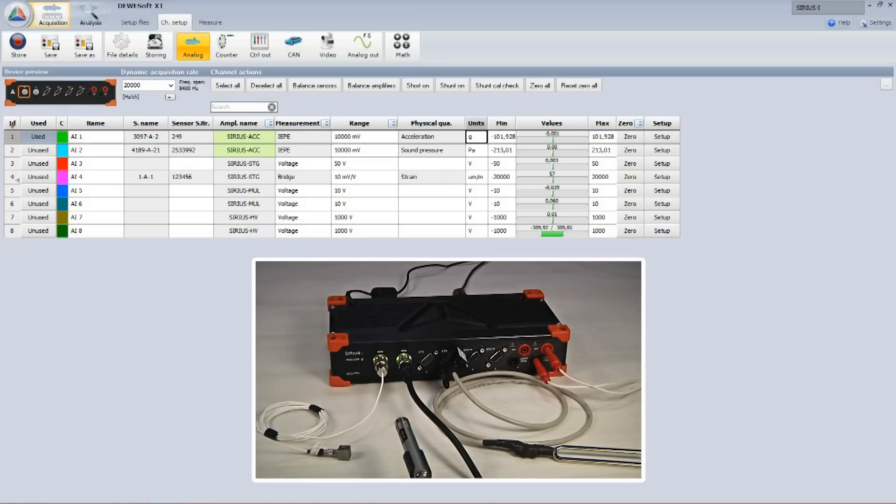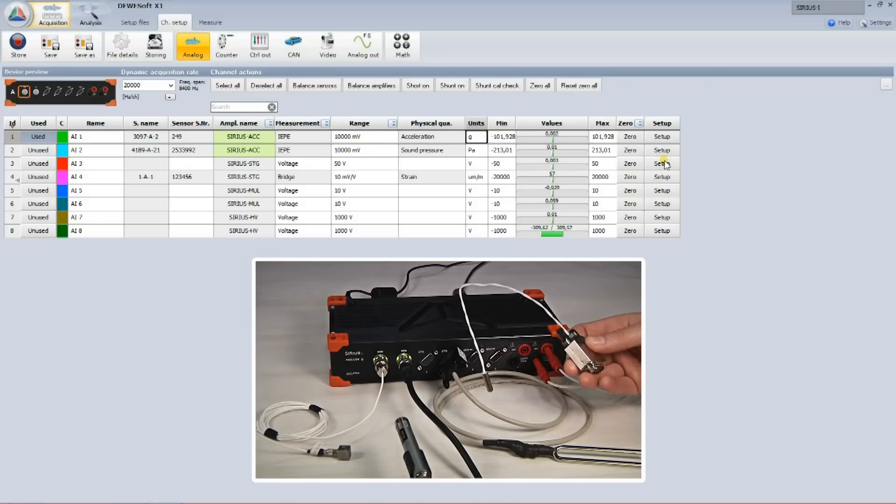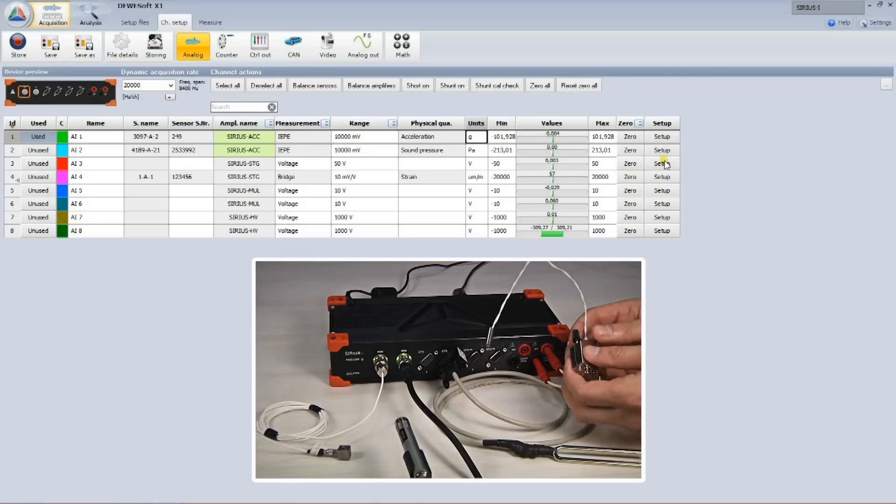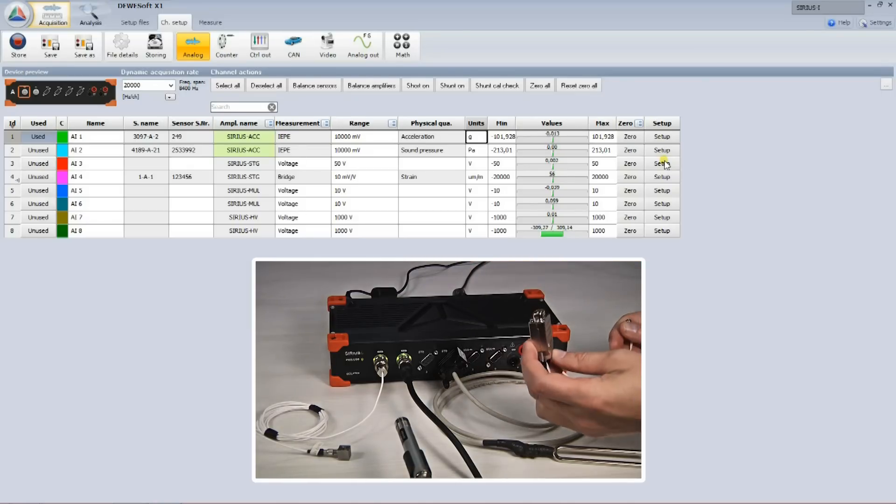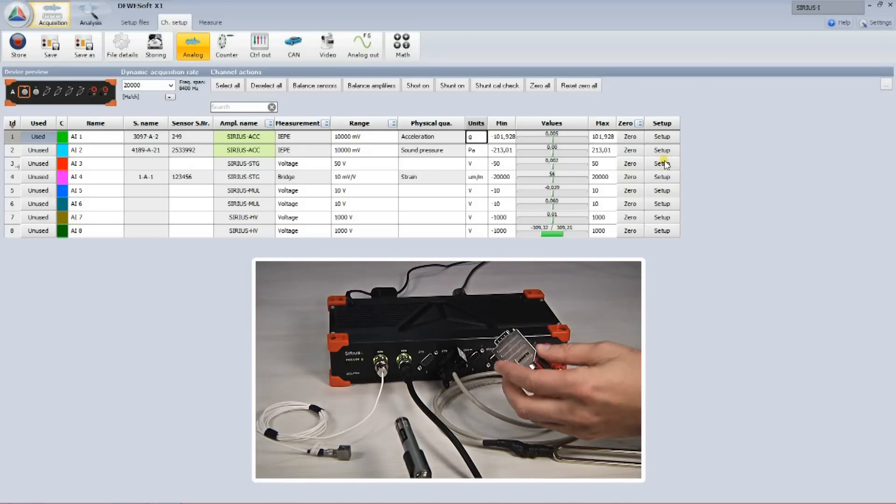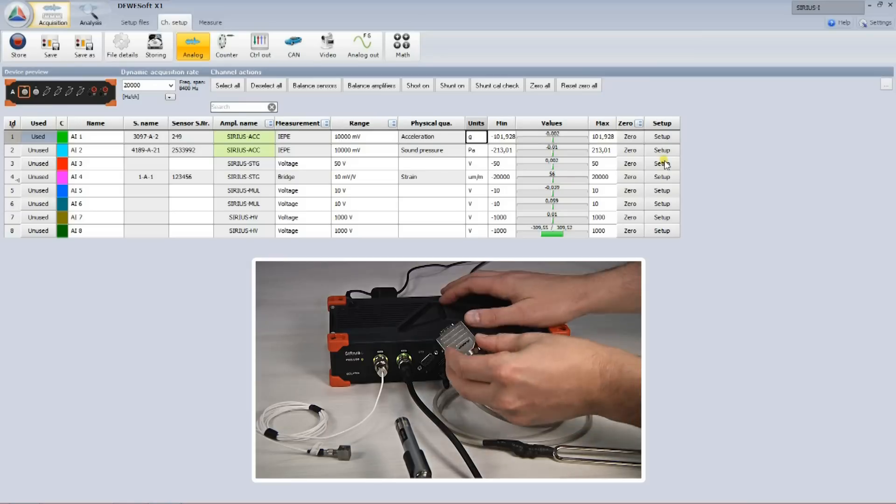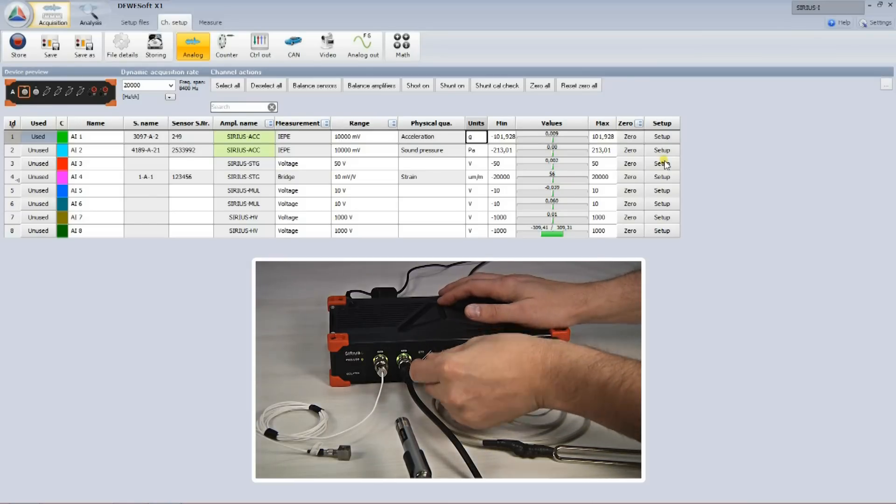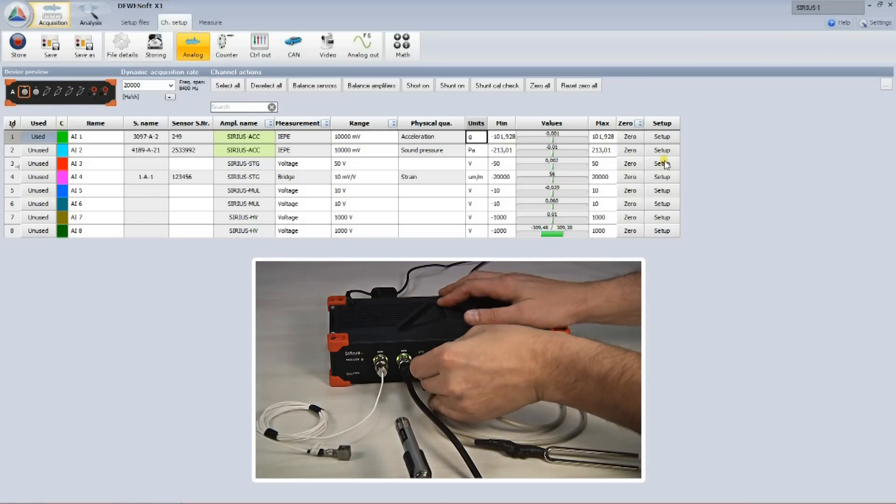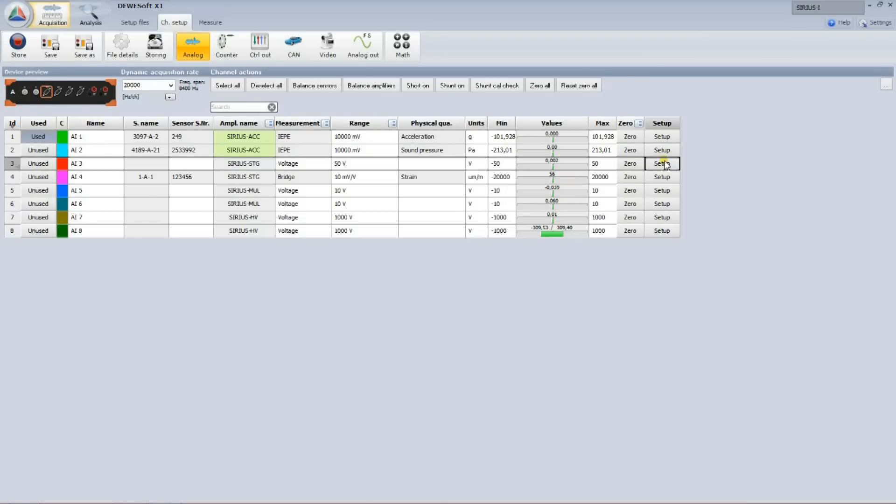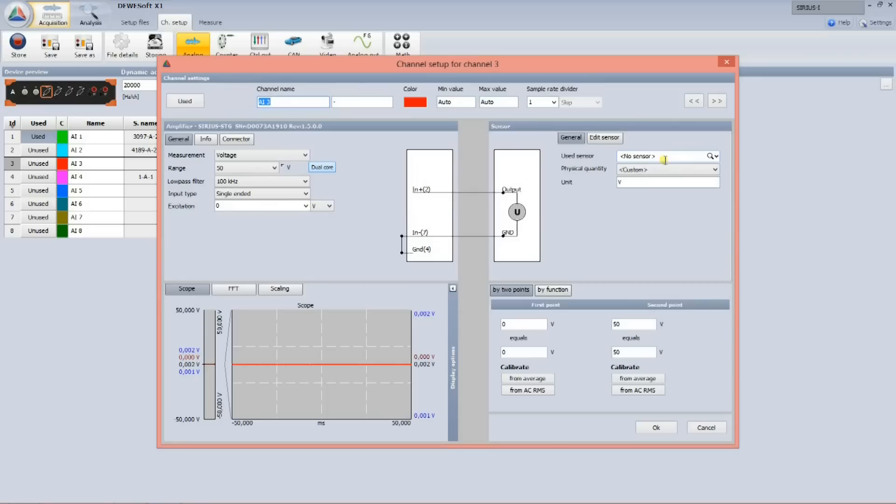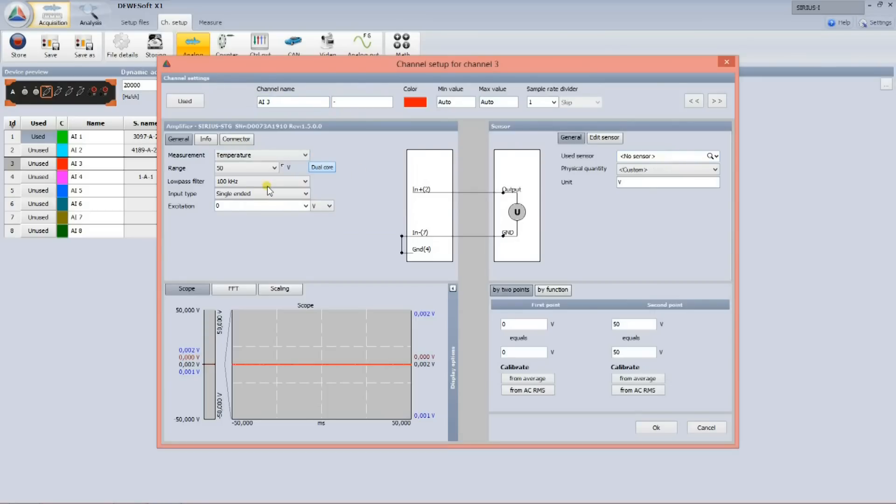So what if I don't have a smart sensor? In fact, it is very easy to create one. Here I have a simple RTD temperature sensor which has very inexpensive TEDS chip built into the connector. When I connect it, nothing happens, because the chip is empty. I need to define it. I go to the channel setup, select the correct amplifier mode and sensor type.